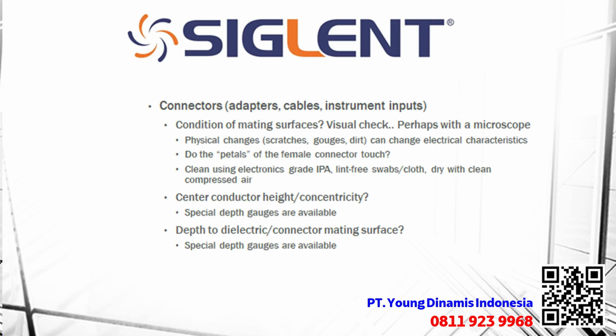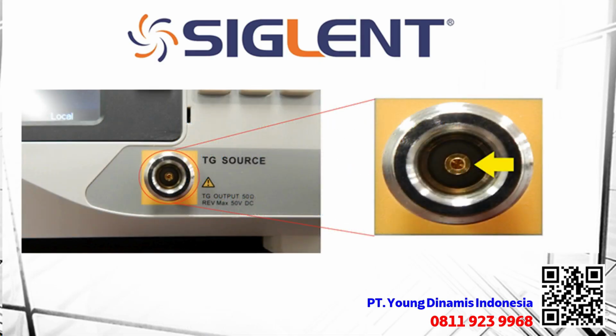We want to take a look at the condition of the mating surfaces for all of our adapters and cables, as well as our instrument inputs. This is usually a visual check, and we're going to possibly use a microscope if we want to take a closer look at those surfaces. We're looking for physical changes such as scratches, gouges, or dirt that can change those electrical measurement characteristics. Do the petals of the female connectors touch? Are they making good contact with the conductors?